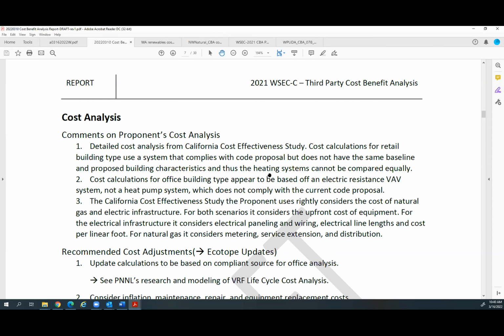Wanted to address some of the statements that were made, one of which was that requiring the cooling compressor to work in heating would not add upfront capacity increases to the HVAC system. And I could agree with that, but I think there is a cost impact to that. I would argue that packaged heat pumps have additional parts and controls that add to the cost. Things like a reversing valve, defrost board, and heat strips. And in general, if you call an HVAC vendor and ask for a price on a gas pack unit and then ask for an equivalent heat pump unit of that same size, you're generally going to see a higher price for that heat pump option. And I don't quite see where that's reflected in the analysis.